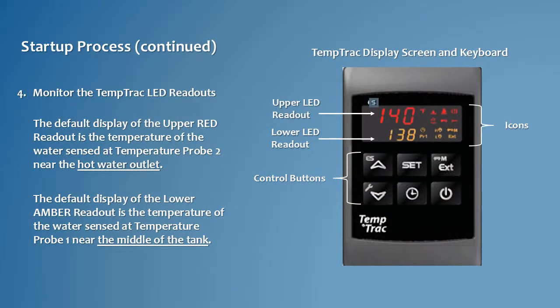Now monitor the TempTrac LED readouts. The upper red readout displays the temperature of the water sensed at temperature probe 2 near the hot water outlet. The lower amber readout displays the temperature of the water sensed at temperature probe 1 near the middle of the tank.